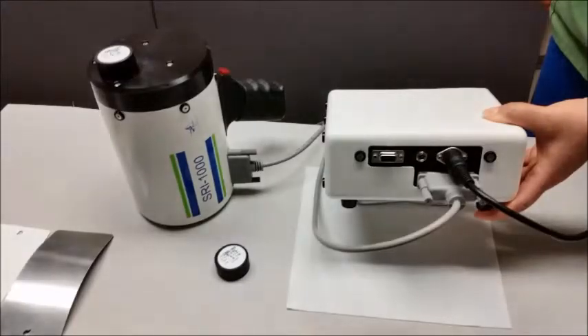SRI 1000 operation. Physical setup. When used in the lab, the SRI 1000 can be plugged into a standard 120 volt AC outlet using the AC adapter. The power supply will accept an input of 100 to 240 volts AC, 50 to 60 hertz, and the head can be placed with the measurement port up for easy placement of samples.